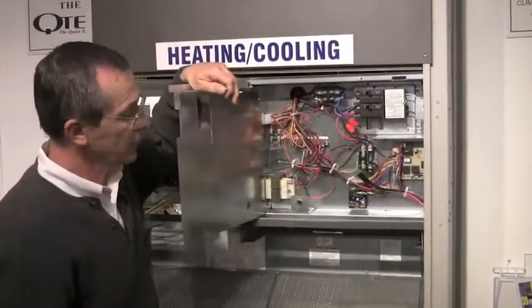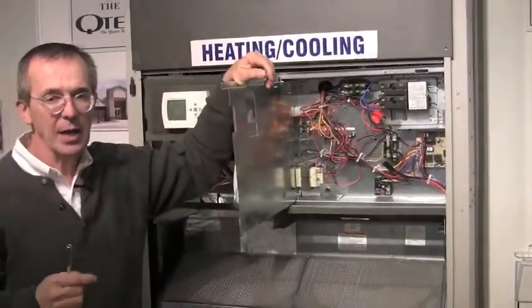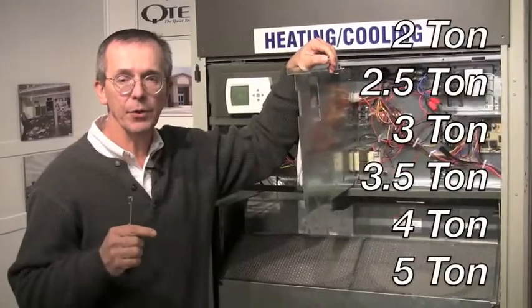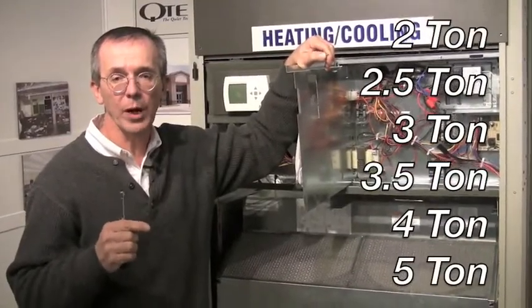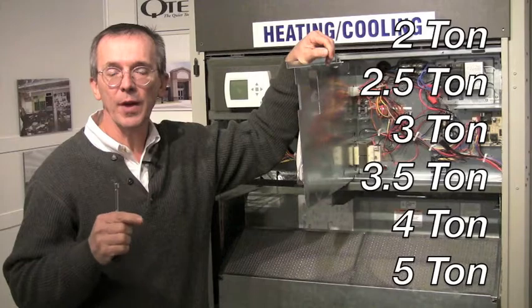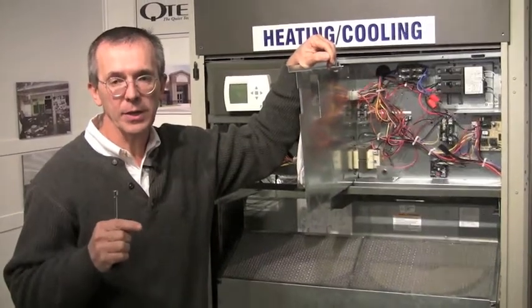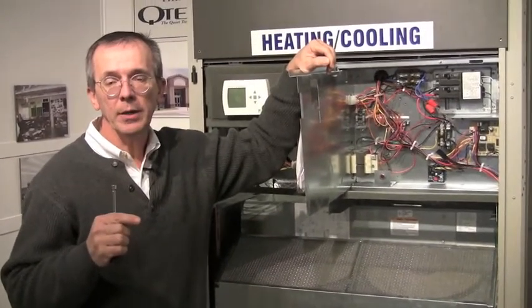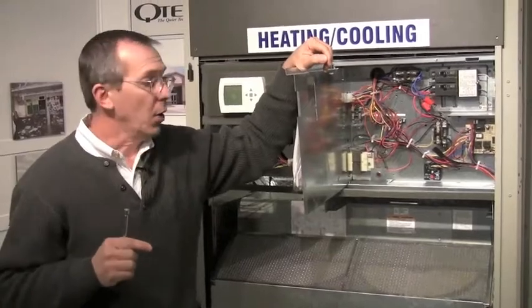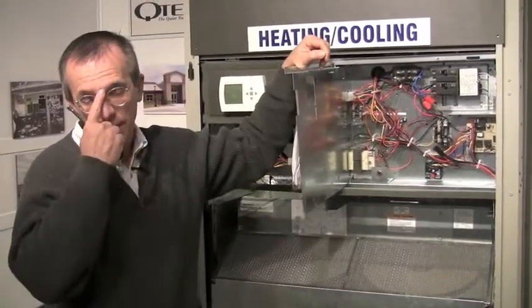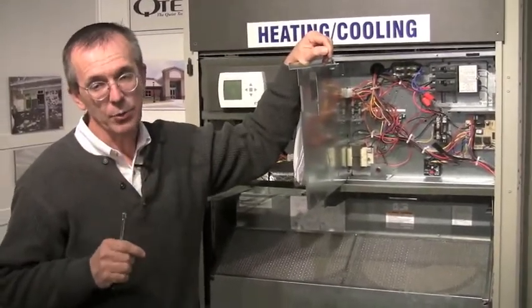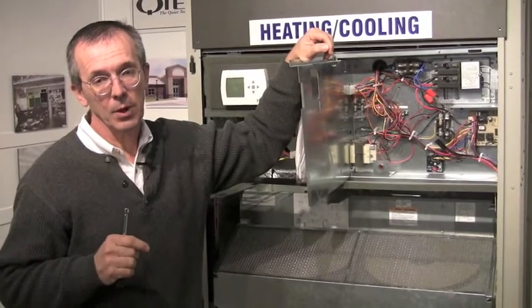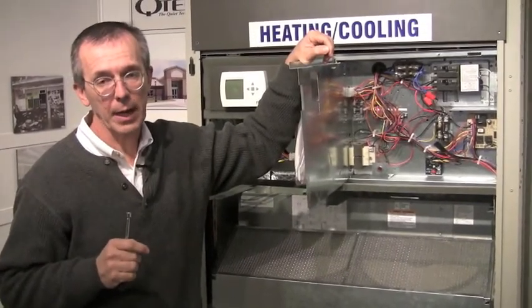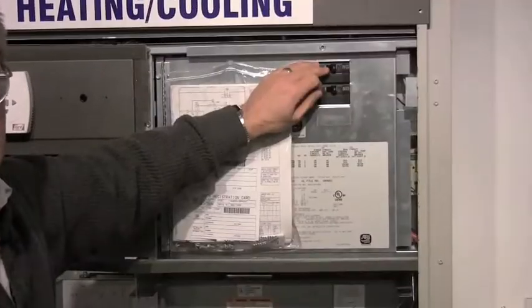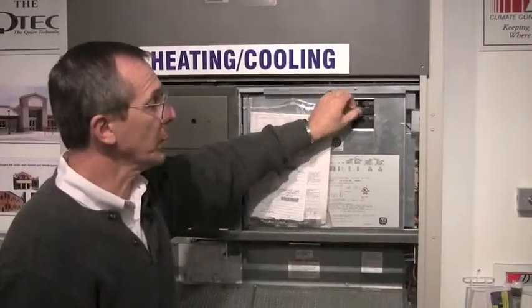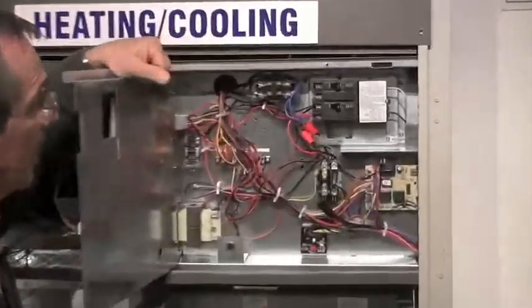of the electrical section. This unit is available 2 ton, 2.5, 3, 3.5, 4, and 5 in single phase and in 3 phase, 208, 230, or 460 volt. This particular unit is a 3-ton unit with 10 kW electric backup heat. If this was a 460 volt unit, this would be a rotary disconnect switch here.